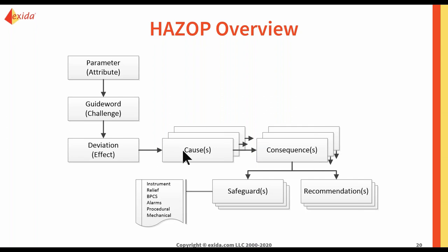And then we're going to move on and talk about the consequences related to this cause, to this initiating event. And the consequence that we talk about in HAZOP is the ultimate consequence, without thinking about any kind of safeguards. Because it is a way to look at the situation, to coin the hazard, and then later we can plug in the safeguards one by one. So it's a kind of elimination process in a way that's going to give you a much more comprehensive, procedural way to look at and also coin the hazard in a more structured and regulated manner.